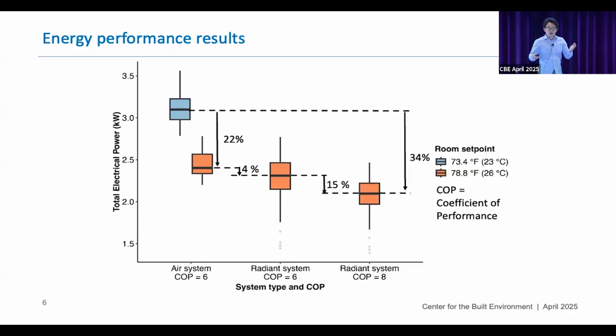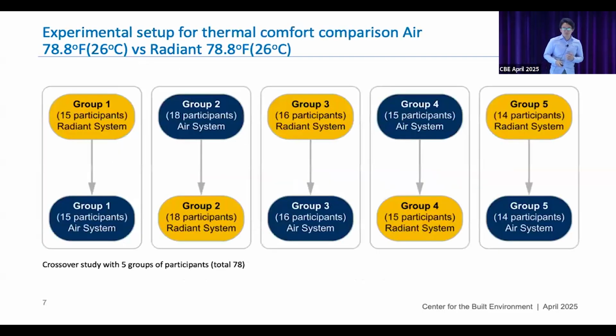So the takeaway here is that separation of latent and sensible loads is important. And if you're able to have two independent chillers to do that, that will have much more energy savings.